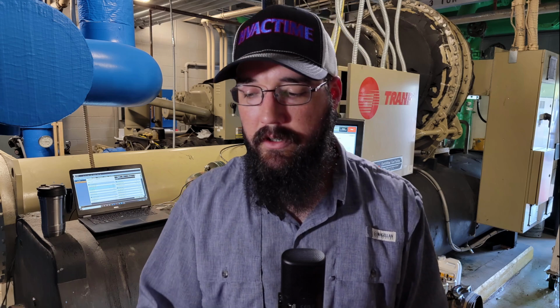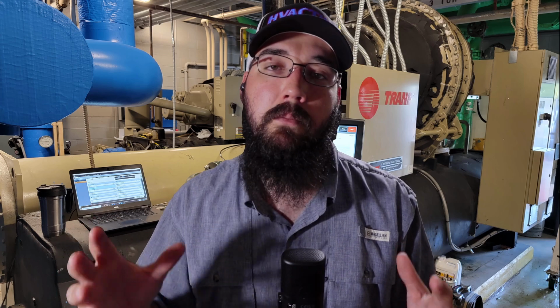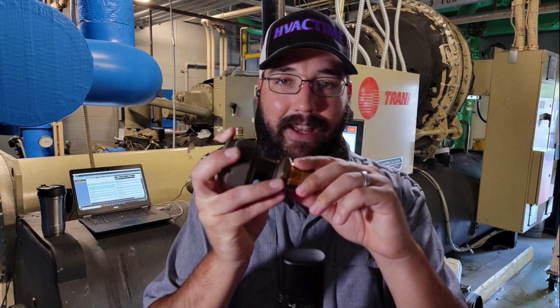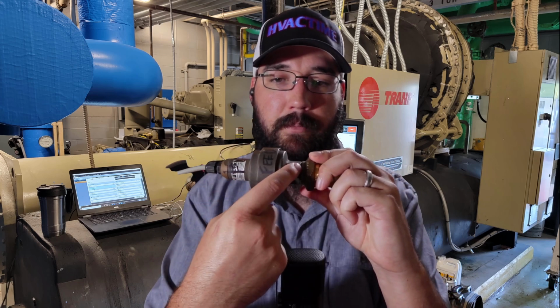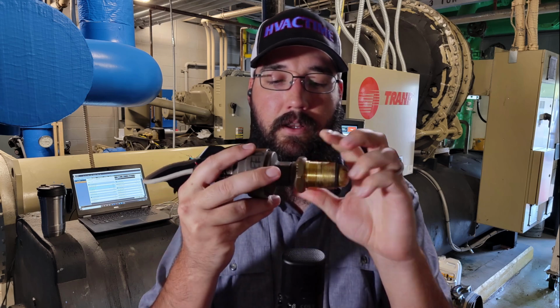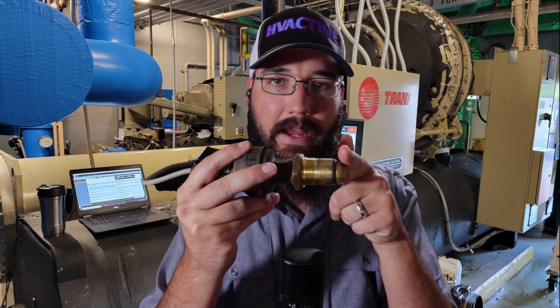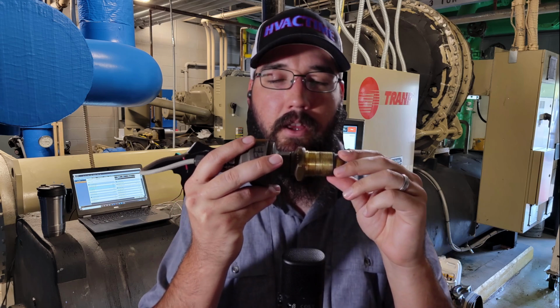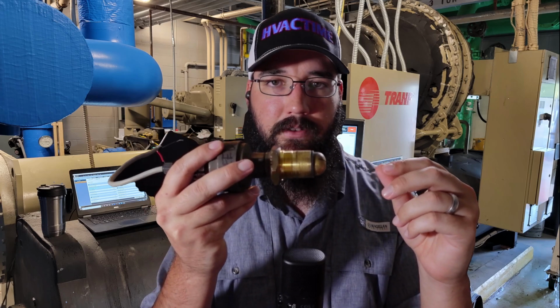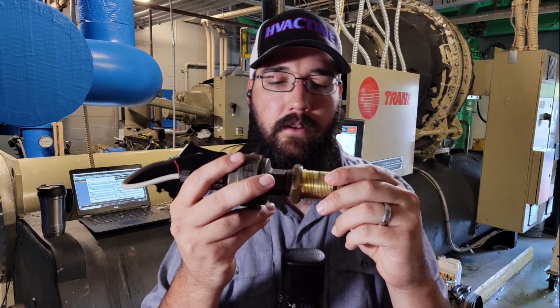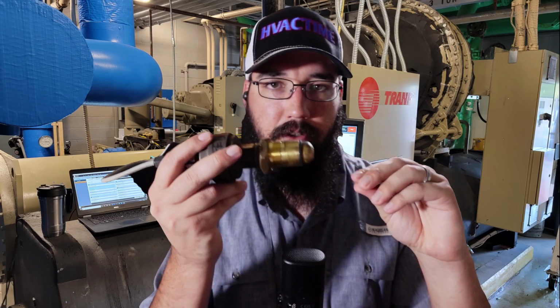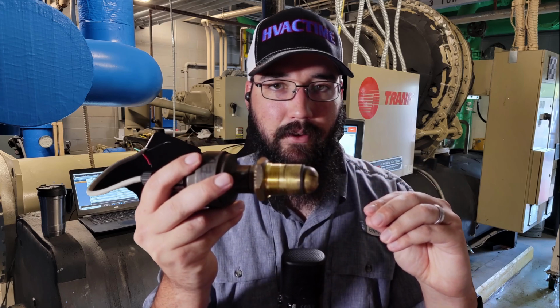If you find one that has bad values, you've just got a bad motor. It's going to lead to replacement. And these valves are not meant to do a motor replacement. So while technically from here up is your motor and here down is just strictly the mechanical part of the plunger, you're not going to separate these and replace that. That's not going to go well. If you're going to replace this, you're going to replace just the whole head assembly itself.